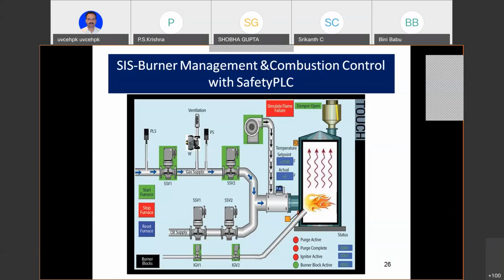So when you start the fired heater for the first time, you have to first purge it. There is a cycle. I know that cycle; my memory is not failing me. Step 0, start the blower and push air into the system. Step 1, after 7 seconds, you check whether there is a mischievous flame floating around there, because something is still burning. You don't want that.